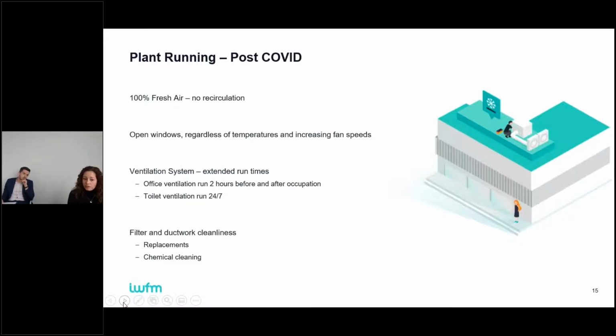This applies not only to the office space supply and extract system, but also to the toilet supply and extract system. Where possible, it's advised that office ventilation systems at nominal speed should be on 2 hours before the building is occupied, stay on during occupation, and continue running for another 2 hours after everyone has left. Especially now as people return to offices, you need to track when people are coming into the building and adjust your settings to allow for 2 hours before, throughout occupation, and 2 hours after.